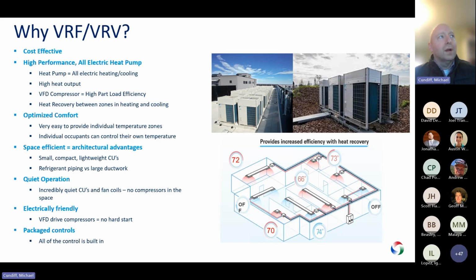You've got the VFD compressor that has a great part load efficiency, and even in a place like Colorado with close to a 0-degree design day, most of the time you're not at 0 degrees. You're somewhere between probably 30 and 80 degrees, and you can get pretty sunny days even in the middle of wintertime, which is nice when you can have the simultaneous cooling and heating.